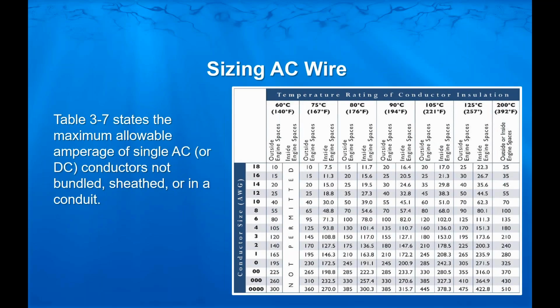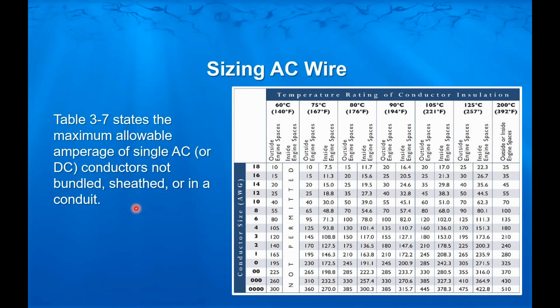And what we're going to look at here, I want to just take notice. So this is for single conductor. So if we look at 10 gauge and we go over to the 105C column. Now, whenever you reference this, you will normally be referencing the 105C. That is the conductor insulation rating. And basically all marine cable, if you're buying the right stuff, is rated for 105C. Per the standards, 60C is for outside engine spaces, which is why it says it's not permitted for inside engine spaces. And 75C is the minimum for inside engine spaces. But if you buy proper marine cable, it will almost always be rated at 105C.